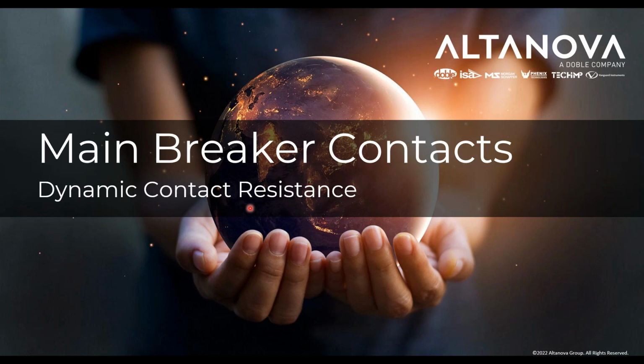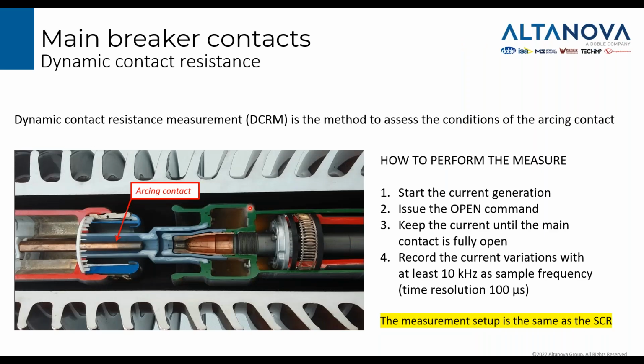The dynamic contact resistance is also a very important parameter to test. When the circuit breaker is opening, the arcing contact is absorbing energy that is generated by the arc.